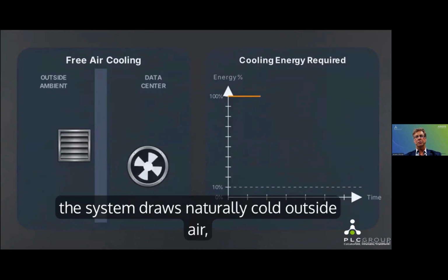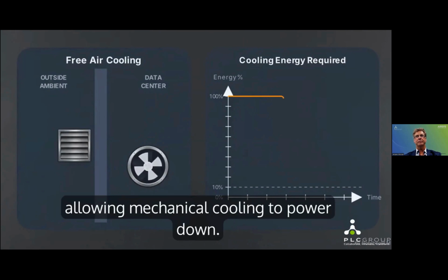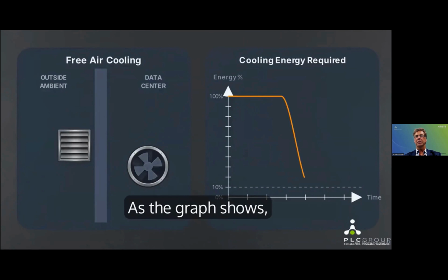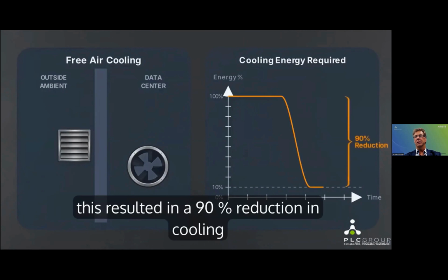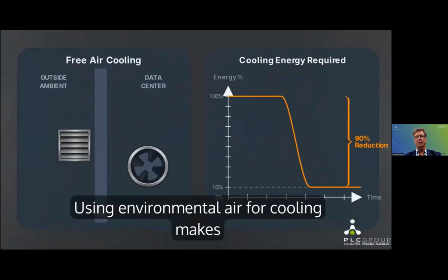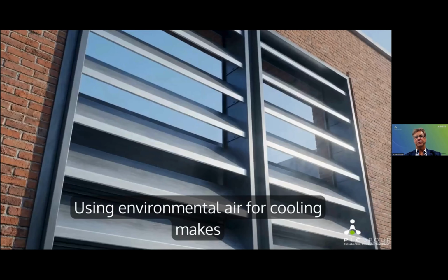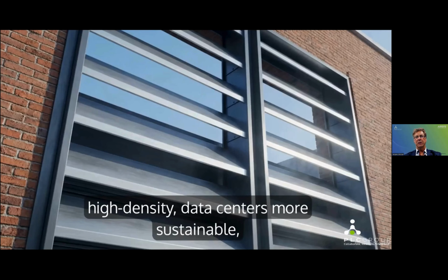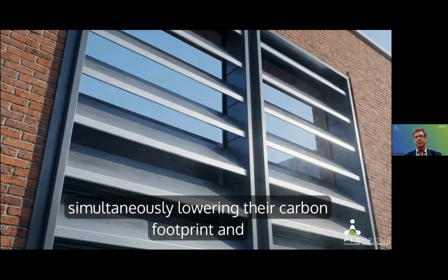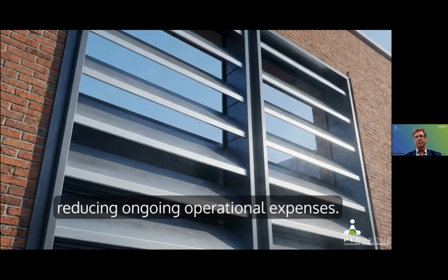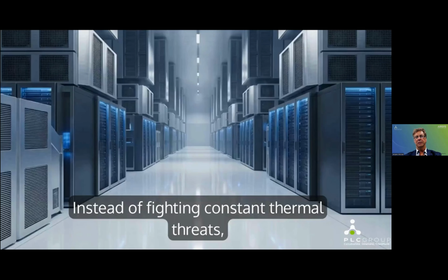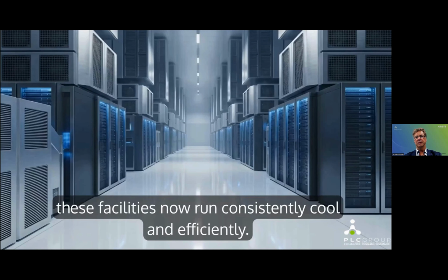During cooler months, the system draws naturally cold outside air, allowing mechanical cooling to power down. As the graph shows, this resulted in a 90% reduction in cooling energy required. Using environmental air for cooling makes high-density data centers more sustainable, simultaneously lowering their carbon footprint and reducing ongoing operational expenses. Instead of fighting constant thermal threats, these facilities now run consistently cool and efficiently.